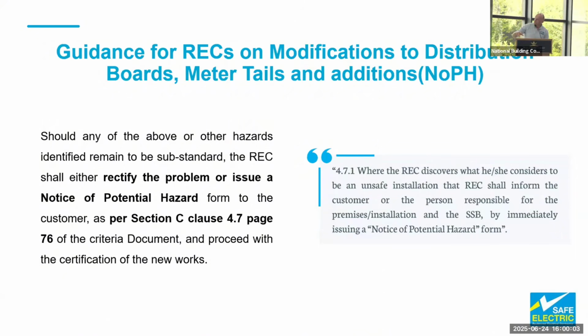So if I just reverse back to give you an example. If we go back to our car charger install, and part of the procedure was for the registered contractor to undertake the testing of the existing RCDs. So he's installed his own RCD, he's tested that, that's functioning fine, he's recorded the test results. He tested the existing RCD for the sockets on the property, and that proves to have failed the test. So if he turns around to Mrs. Murphy and says, I'm obliged to test your existing RCD, unfortunately that has failed the test, and Mrs. Murphy is saying, I only paid you to do the car charger. So the contractor's in a bit of a dilemma here, isn't he?